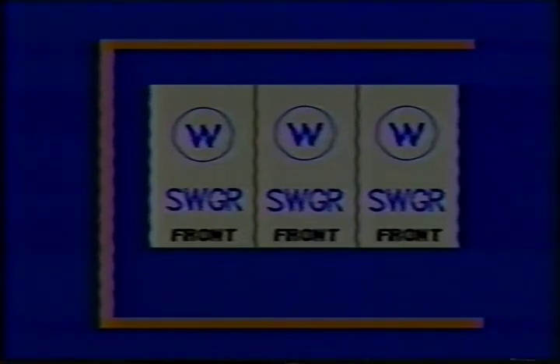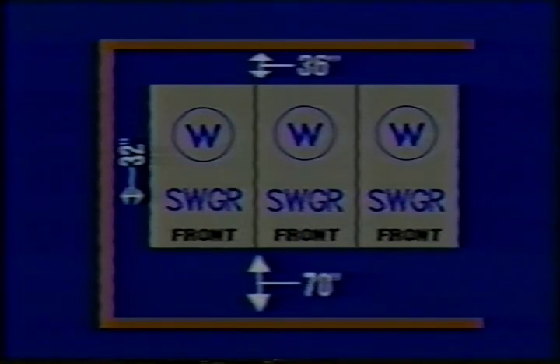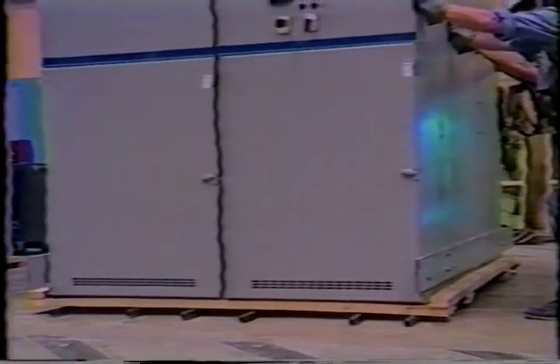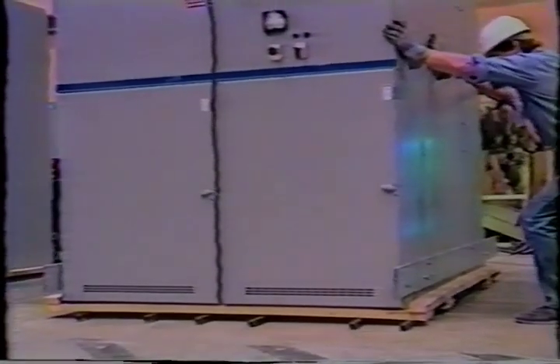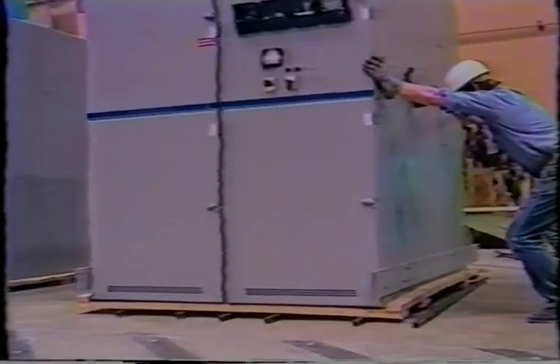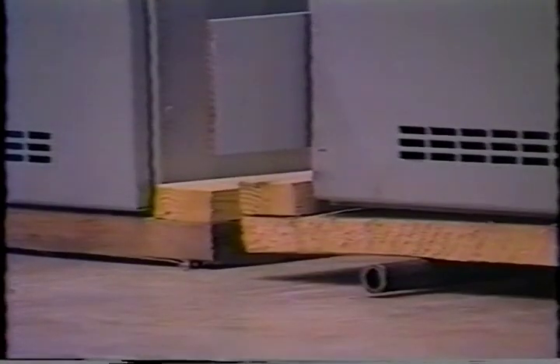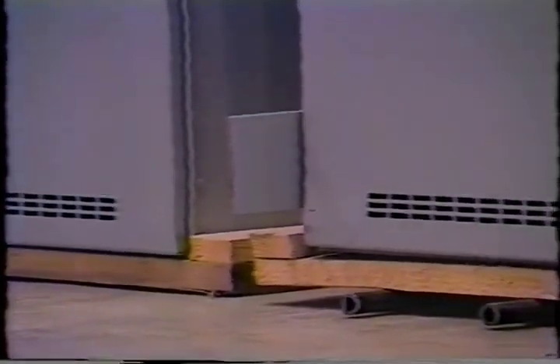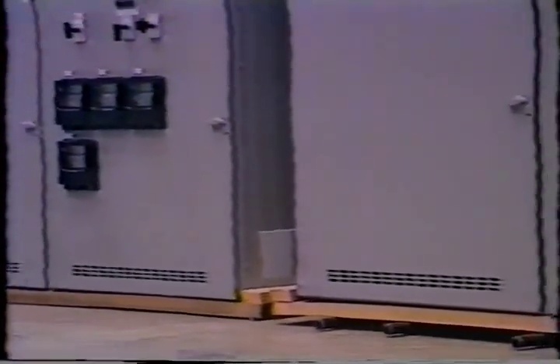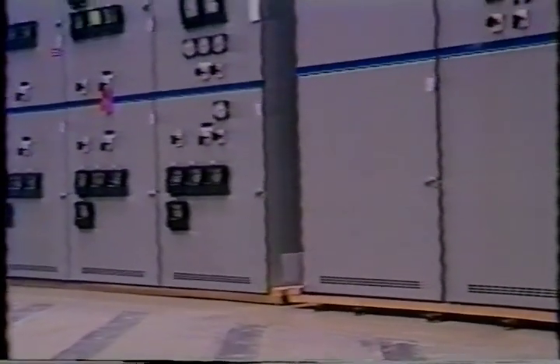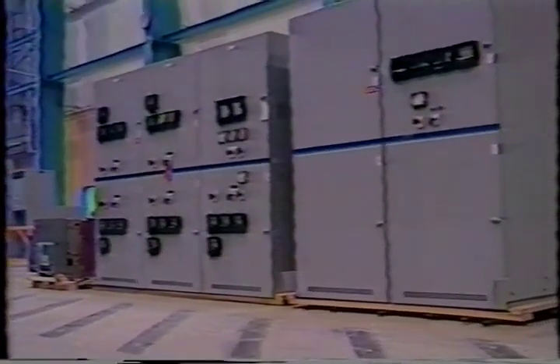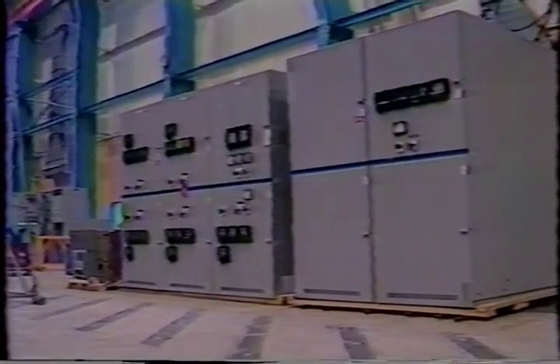It is important to locate the switchgear so there is adequate space at the front, sides, and rear of the equipment. The recommended foundation consists of steel channels embedded in a level concrete floor. Keep the shipping skids on each group until it has been moved to its final installation position. The skids help protect the base of the switchgear and reduce the risk that it will be damaged or distorted during the move. When installing multiple shipping groups, start with the middle group and work outward.